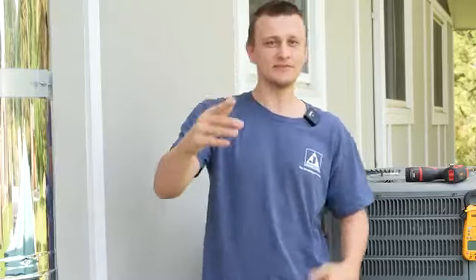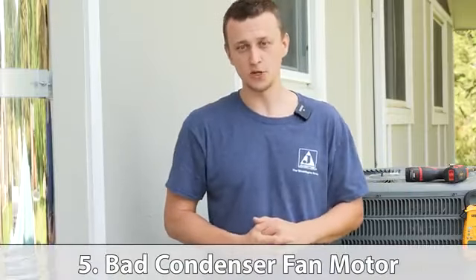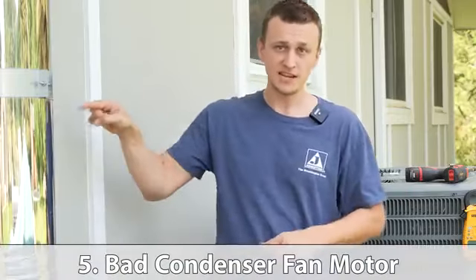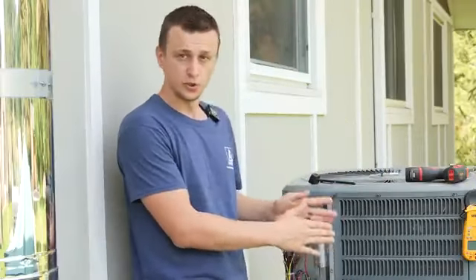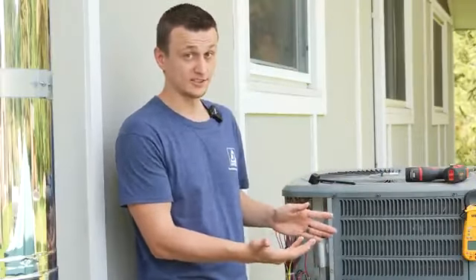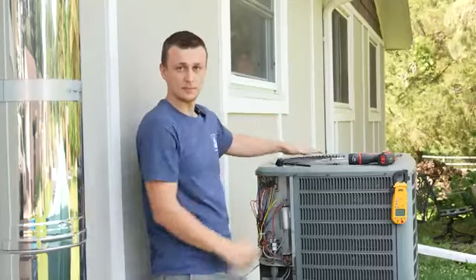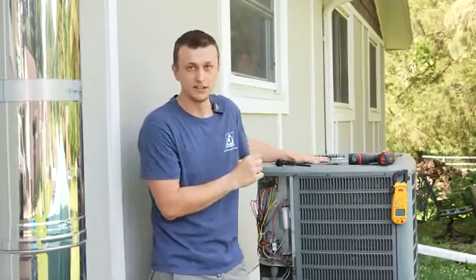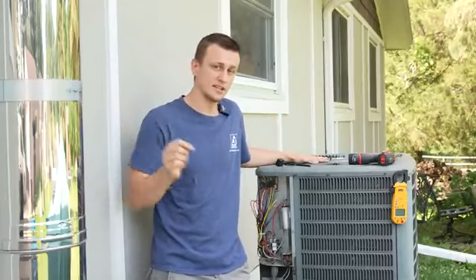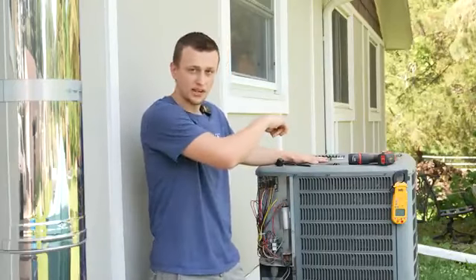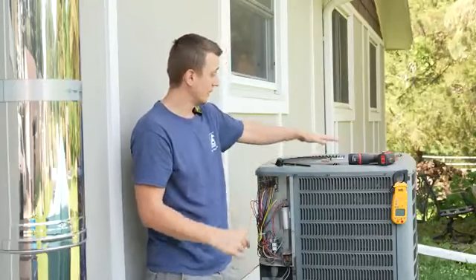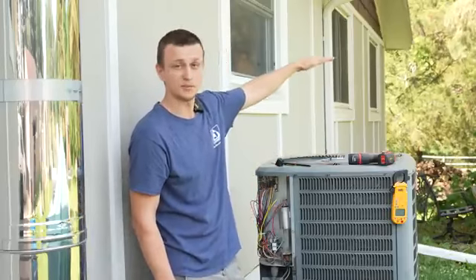And reason number 5 is a bad condenser fan motor. This one is pretty obvious. The fan inside is running. The compressor usually will be running until it overheats. But the condenser fan motor on top of the unit, that will not be running. Oftentimes, if you turn your AC on and it runs for a couple of minutes without the fan running, if you go outside, you might even see some smoke or steam coming up from your unit.